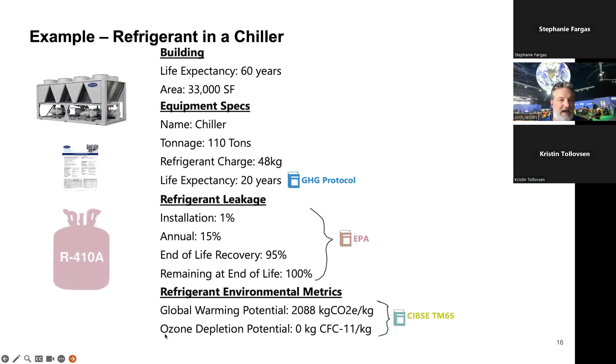That total refrigerant loss and environmental impact, we try to put numbers on it, but when you do it over its lifetime, the lifetime refrigerant leakage, not just end of life, with annual leakage over 20 years plus end of life recovery -- we do recover some, not as much as we should -- the lifetime refrigerant leakage is 146.88 kilograms. Plus the total refrigerant GWP emissions is 306,685 kilograms per CO2 equivalent. So this is the actual in-use phase. This is the embodied phase that we're losing.